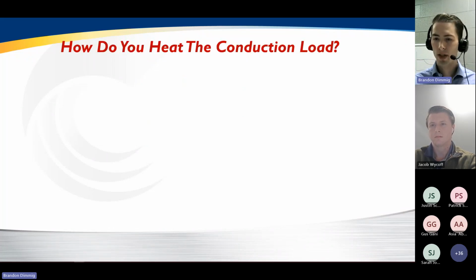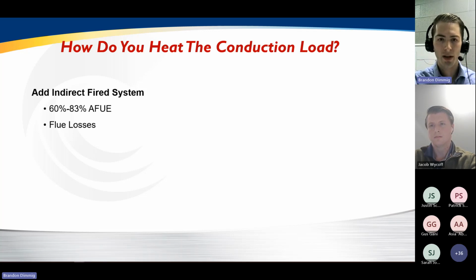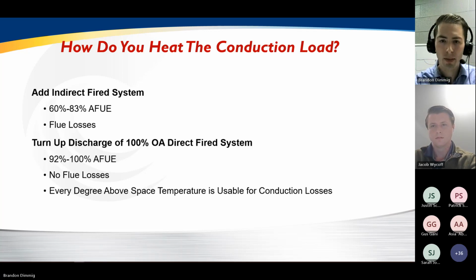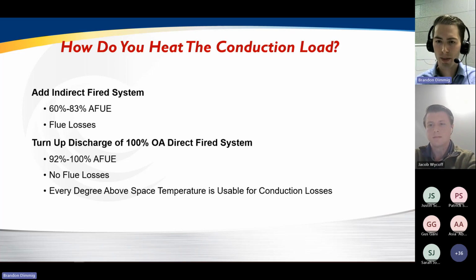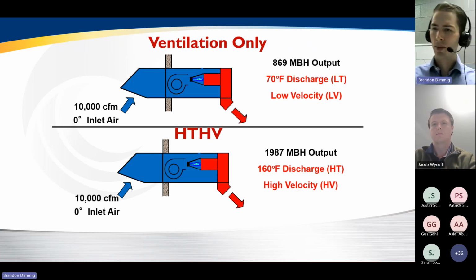But then you say, well, what about the conduction load? What about the skin losses? Because again, as we mentioned, it's a big part of the heat load. So one, you could add more indirect fired systems. You could add infrared heaters. You could add a number of different things to cover the balance of the heat load. Or you could take that same direct fired unit and increase the discharge temperature. Every degree that the discharge temperature is increased above the space temperature is usable to meet the conduction load of the building. So let's do a comparison here. We have the same 10,000 CFM unit in each case, bringing in 0-degree air. The first case we just saw discharged at 70 degrees, and you've got an 869 MBH output.